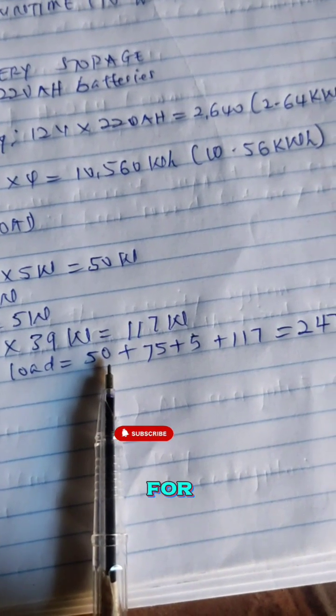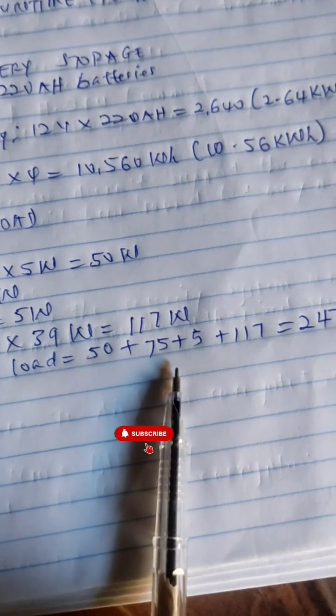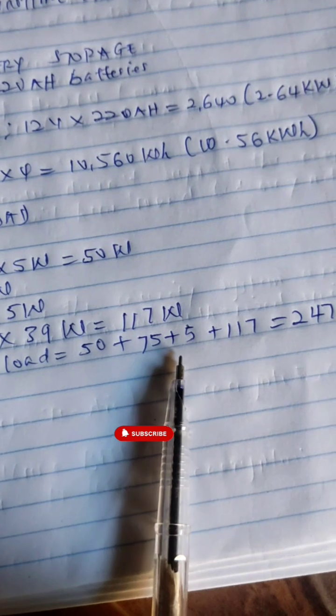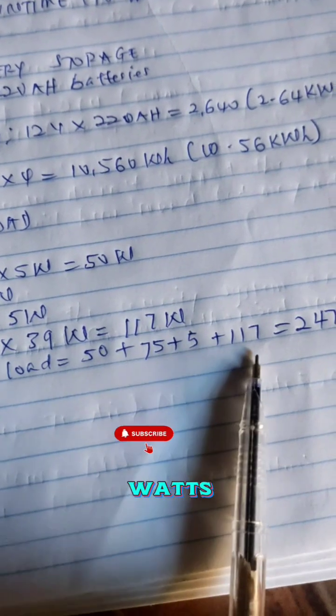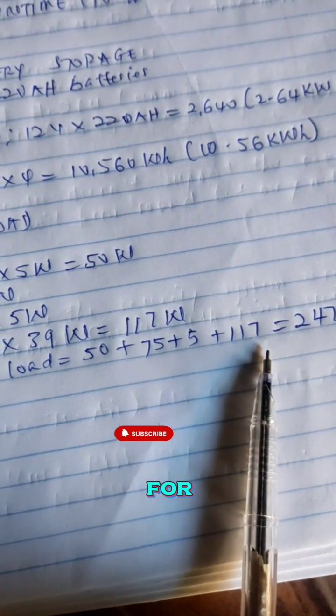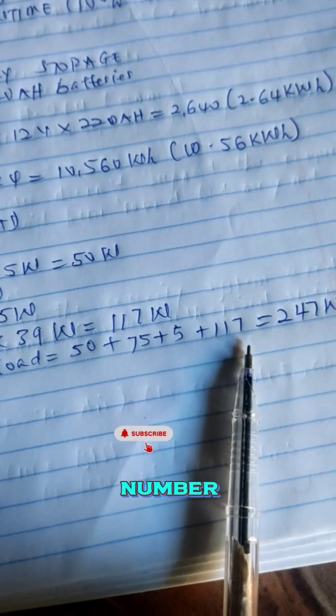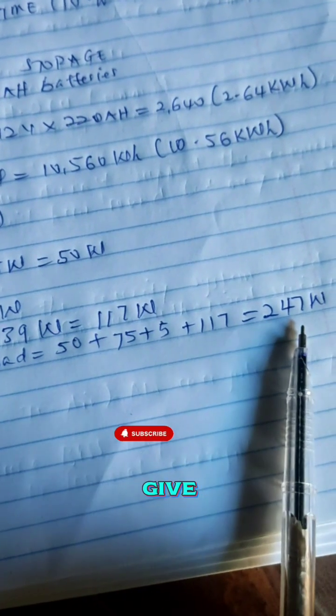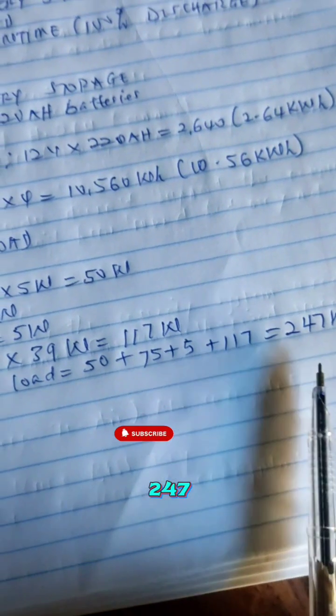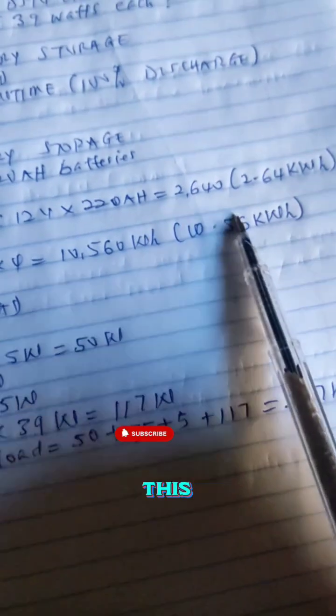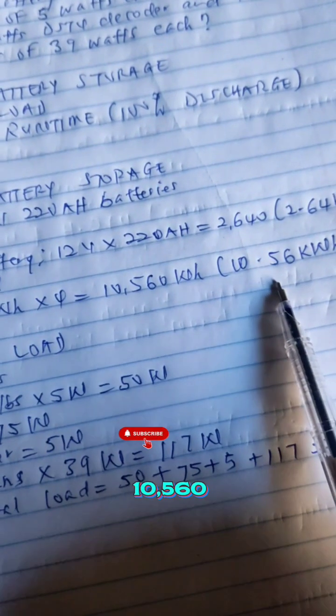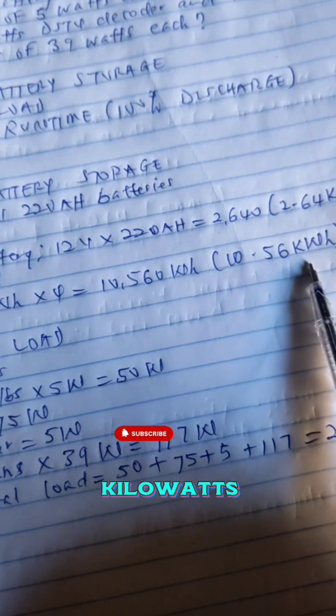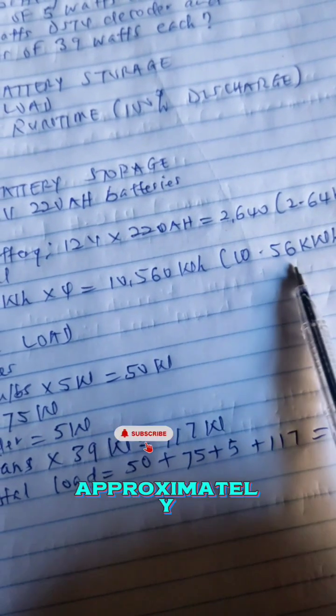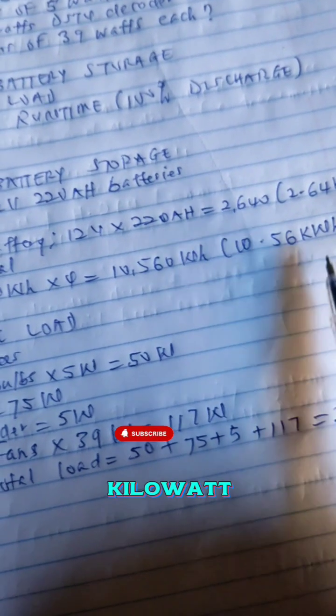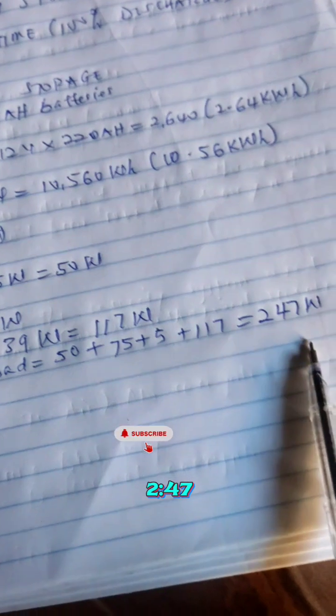50 is for total bulbs, okay? 75 is for TV. Decoder is 5 watt. Then 117 watt is for the total number of fans, which everything will give us 247. So now we have what? For kilowatt, we have 10,560 watt-hours. Understand me? So approximately 10.5 kilowatt-hours, while the load is 247 watts.